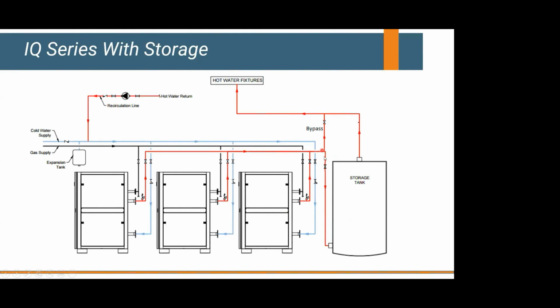If we want to prove to the owner that tankless works, we're going to isolate off the tank, open up the bypass, and see if the heaters can track their load. Okay, now if there is a big dump load or some concerns, this simply acts as a big piece of pipe over here. We don't have a dedicated pump circuit to it. Our goal is just to keep that warm. So if there's a big dump load, it can be met off of the storage tank.